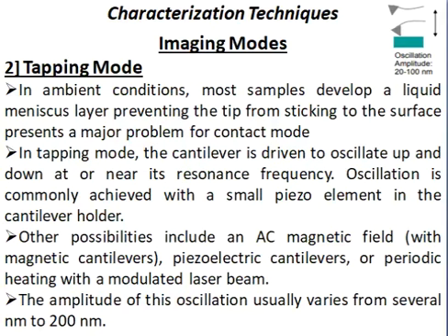In tapping mode, the cantilever is driven to oscillate up and down at or near the resonating frequency. Oscillation is commonly achieved with a small piezo element in the cantilever holder. This piezo element will be provided with a certain amount of power, that is electricity, so that it can vibrate at a particular frequency.